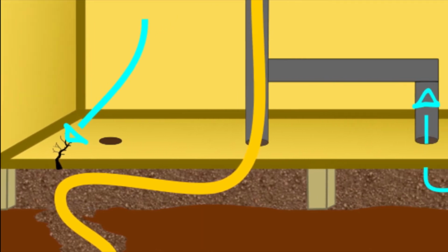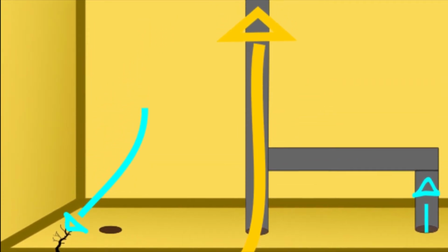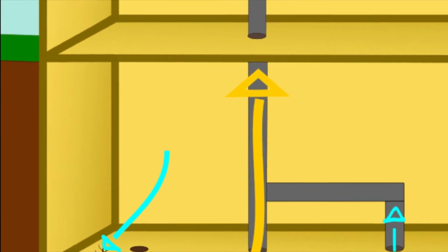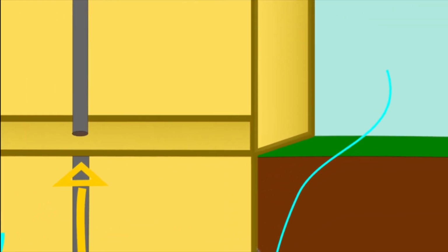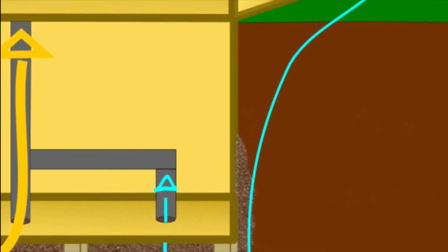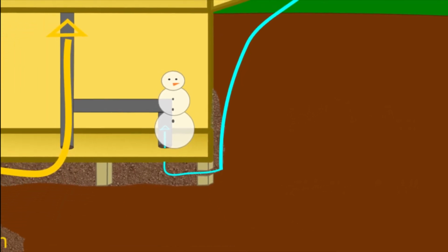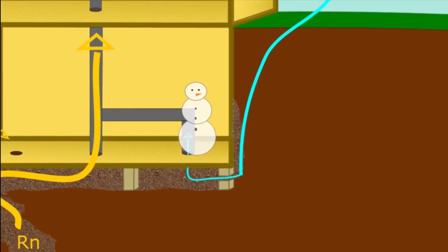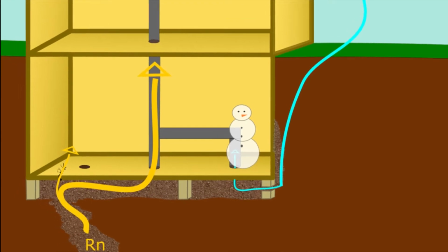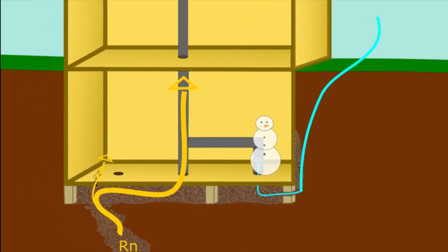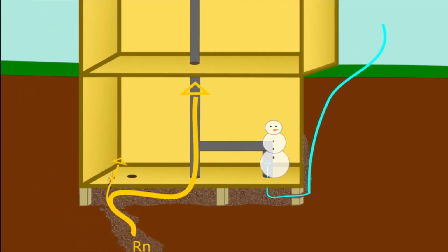The flow through the crack is reversed and the basement air is drawn below the slab and exhausted with the radon fan. The problem with this method is that a lot of energy is wasted sucking in clean air from the outside, and in the winter this leads to cold walls and floors. It also lowers the suction on the other side by pulling in outdoor air, plus now you have a large unsightly jumper. Even worse, the problem might not have even gotten solved.